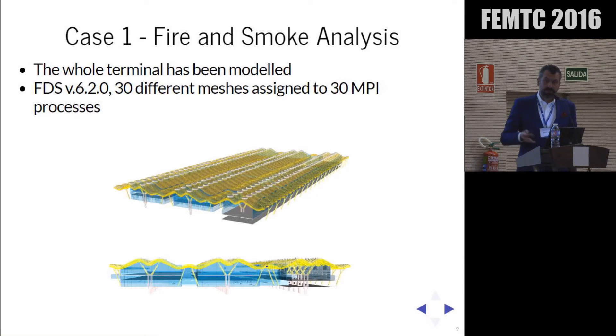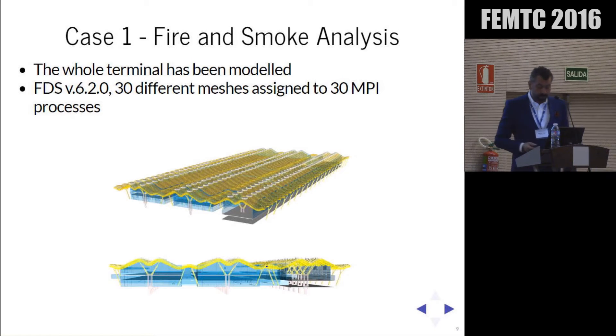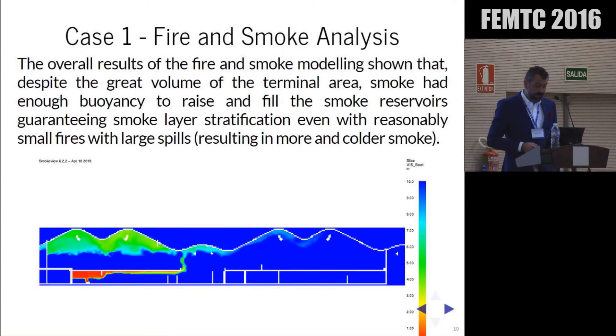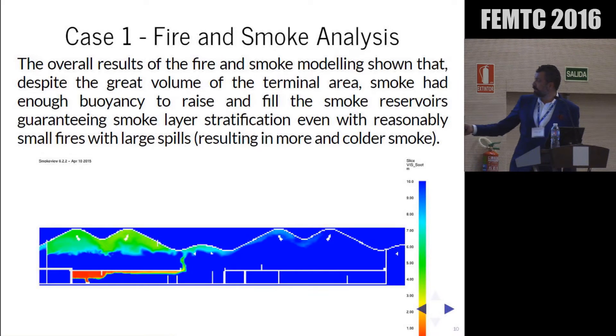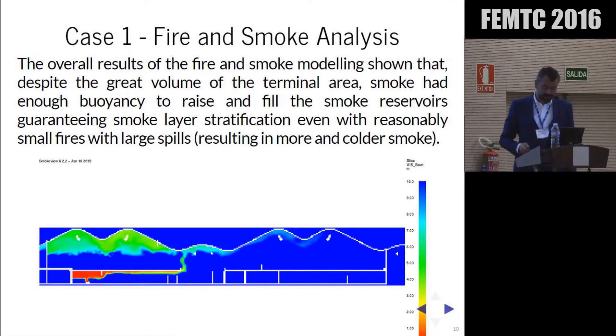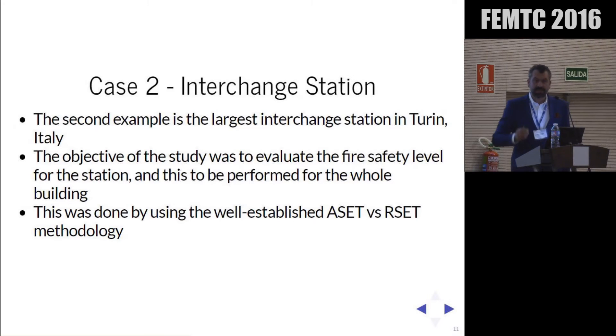We also did fire and smoke modeling for the same terminal. We modeled the whole terminal — a massive model split into 30 different meshes, as you can see in the Smokeview picture of the FDS model. The overall result showed that despite the great volume of the terminal area, smoke had enough buoyancy to keep itself at the higher level, and it was safe for occupants to evacuate the building. This is just one picture of a quite complex project.